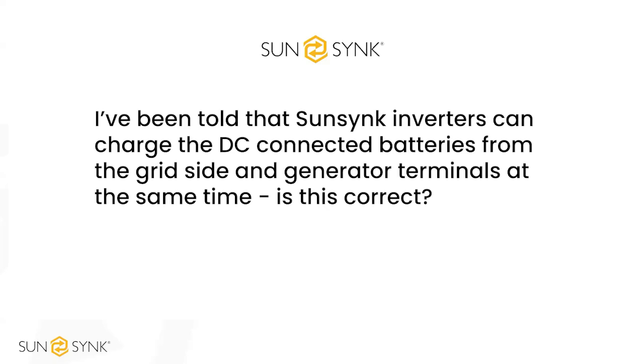I've been told the Sunsynk inverters can charge the DC connected batteries from the grid side and gen terminals at the same time. Is this correct? So obviously grid side, no issues whatsoever. And then the gen terminal. If someone's got a backup generator connected, that backup generator would only kick in if there is no grid connected. But if there is a grid outage, the backup generator would charge through the gen terminal. Apologies if I've not understood that question correctly.